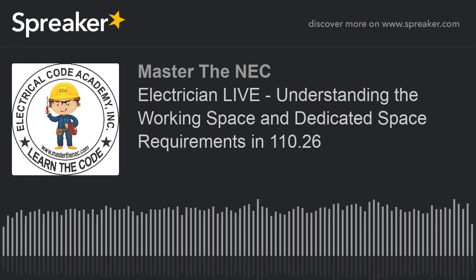Okay, it goes on to say, within the height requirements of this section, other equipment or support structures such as a concrete pad associated with the electrical installation and located above or below the electrical equipment shall be permitted to extend not more than 6 inches beyond the front of the electrical equipment. Okay? So this is basically giving us the allowance to say, okay, we have this height restriction, but I could have other equipment that are going to extend into or be the supporting structure, such as having this equipment sitting on a concrete pad. And we have to be aware that that's what we can do.